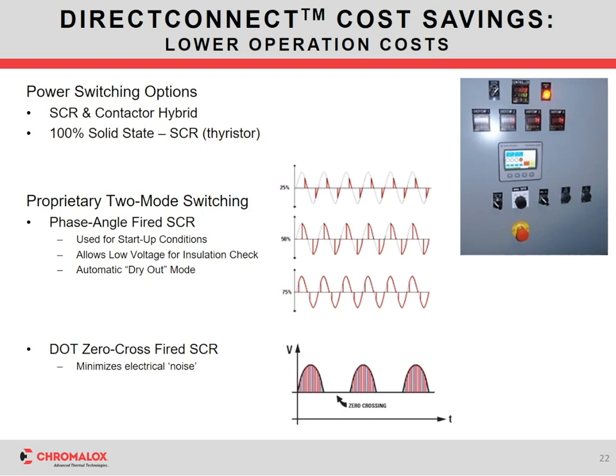So generally speaking, a phase angle fire can really cut the wave down to only the power you need. However, it also tends to generate electrical noise that some people may not want in an application. Fortunately, phase angle is only needed during the startup phase of a heater. And what that's used for is to ensure that the megohm check and any dry out that would be needed can be done properly before the system powers up to full power output. And again, phase angle is only used at very low power, and that's more of a self-check. During normal operating conditions, that's where the zero cross fired SCR is used.